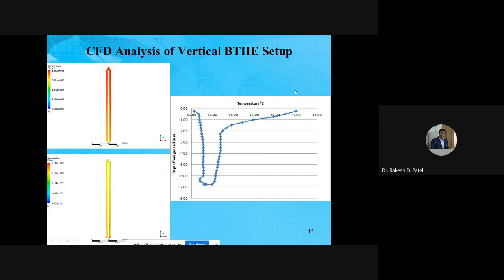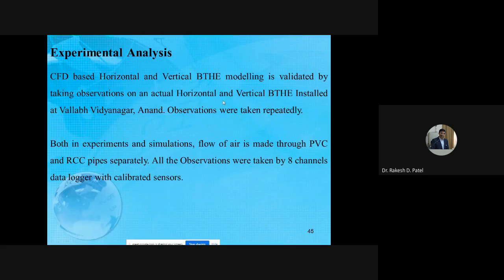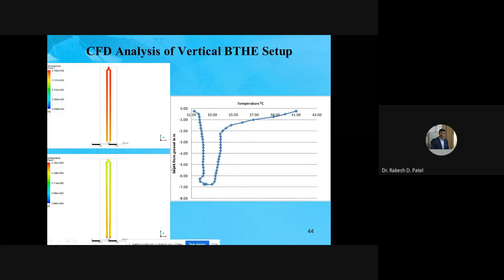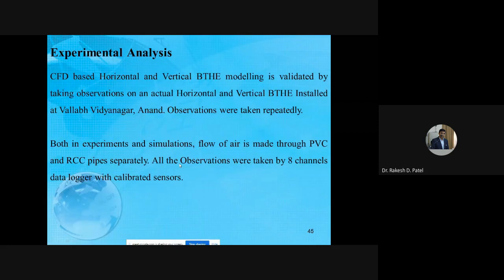Now, CFD analysis of the vertical heat exchanger. This is the condition for the winter. The inlet condition of the heat exchanger is 31 degrees centigrade, and the outlet condition is 41 degrees centigrade, from the CFD simulation of the heat exchanger. So approximately a 10 degree temperature difference is achieved in the vertical heat exchanger in winter conditions. Now, experimental analysis. All the results of the CFD analysis and analytical analysis are validated by the experimental analysis.